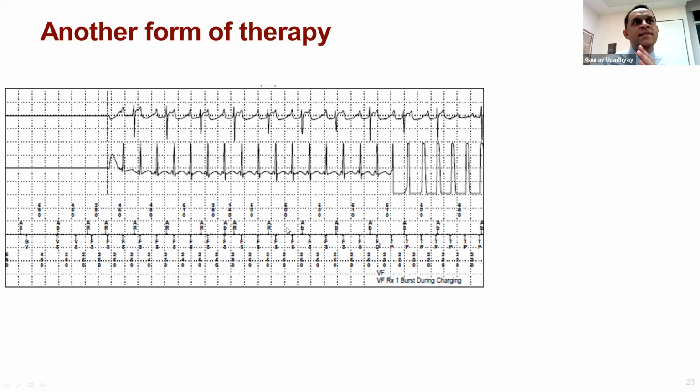The device only sees what it notes. Does that make sense? You very quickly said, oh wow, there's far field ventricular activation that I see with my human eyes on the atrial channel. But the device, the way it's programmed, doesn't see it except for right here. There's an atrial blank and an atrial refractory. Otherwise, it doesn't see those signals. You see what I'm saying? The device only sees what it marks.